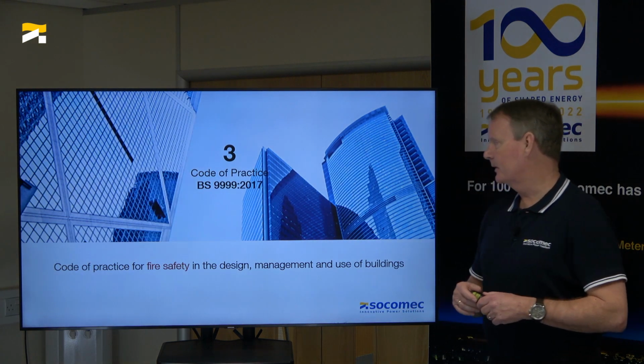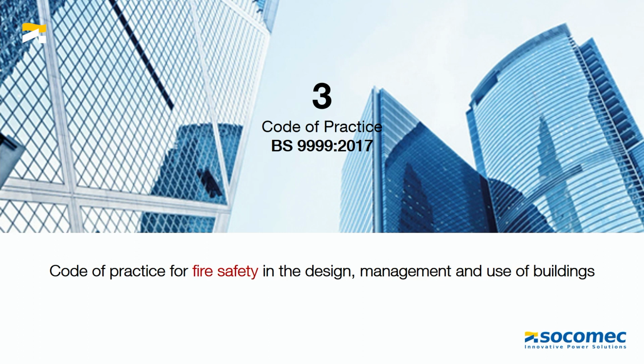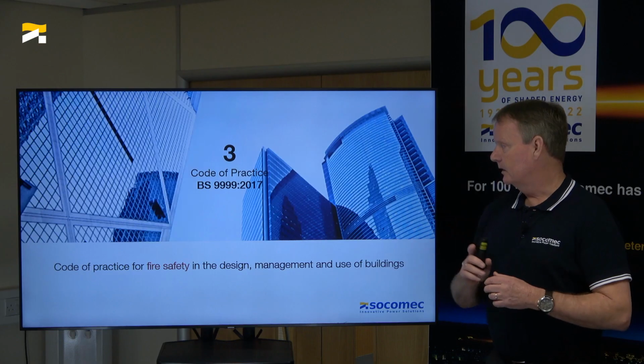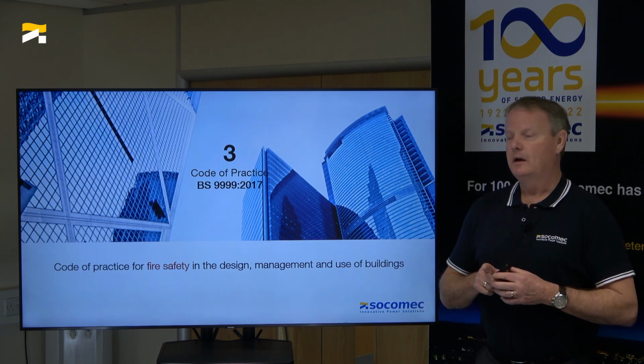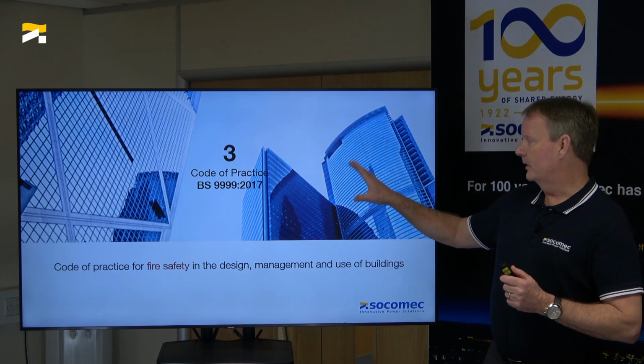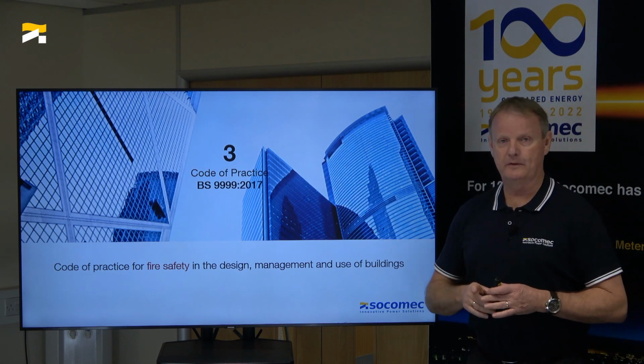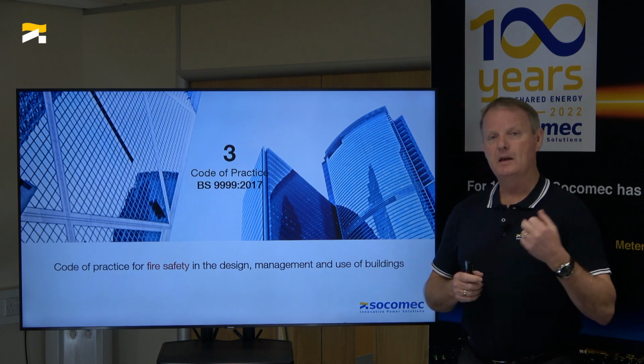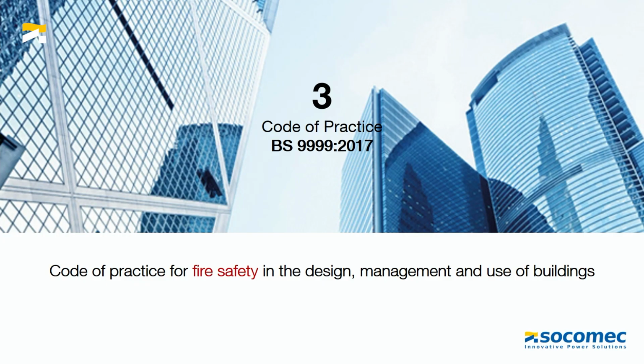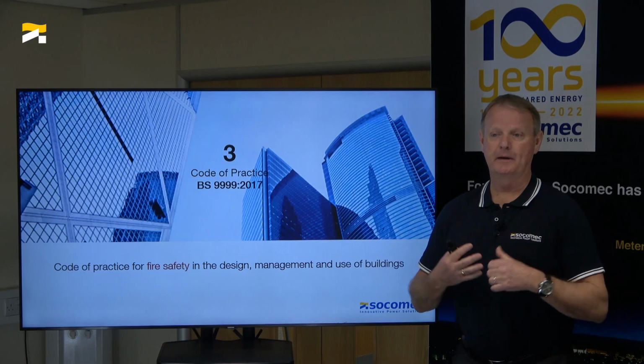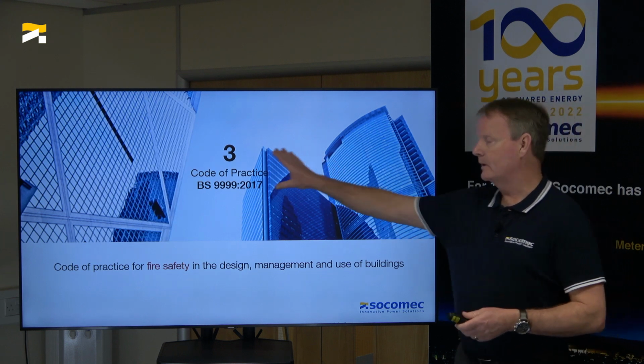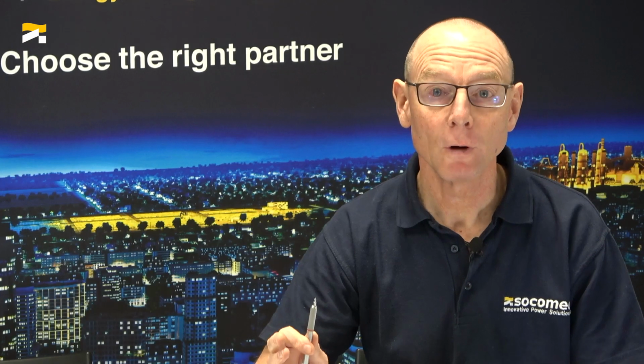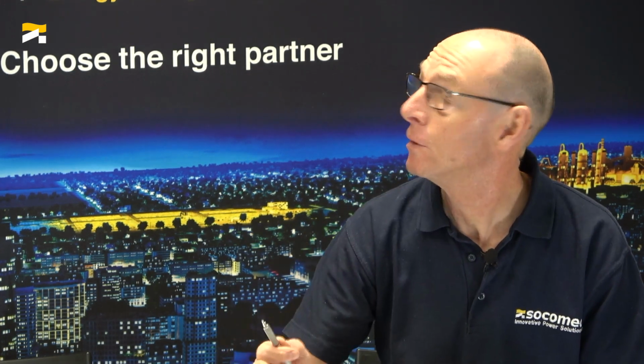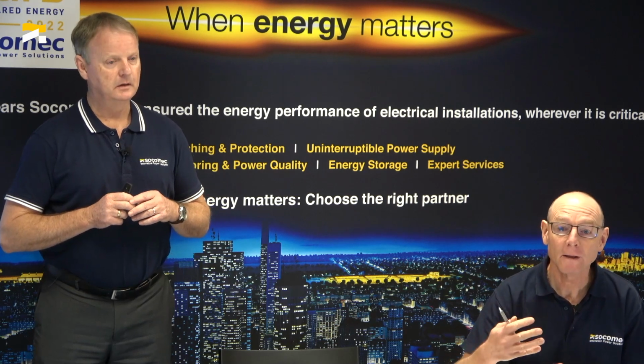Most people would know this one, BS 9999 2017, the code of practice for fire safety in the design, management and use of buildings. This is really around commercial buildings over 4 stories - there's obviously another standard for domestic dwellings. This code of practice is all-encompassing, so even though we're going to talk about some electrical parts of it, it also pertains to lots of other parts: firefighting lifts, fire systems, cables, fire rooms, even doors. We come from the electrical industry so we're going to focus on the electrical part, but it is an all-encompassing document. It's all about safety, looking at the use of the building, how it's going to be used, the occupancy rate, and understanding what is required to make it a safe place to visit, work in, or attend.